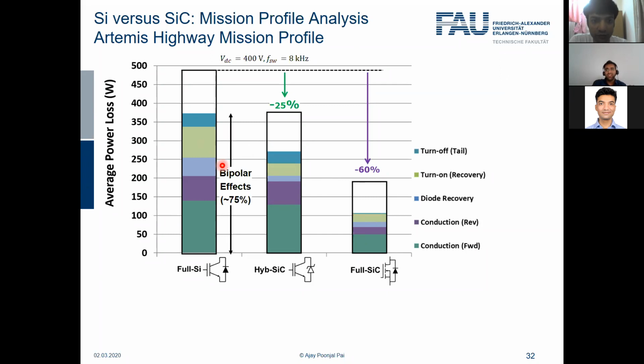Now what is missing is the tail. The IGBT has a tail current, which is missing in case of a SiC MOSFET. But in a hybrid device it still exists, because we are using the same IGBT and changing only the diode, and tail current is not affected by the diode. So we are already saving quite a lot of power losses by using a silicon carbide MOSFET. What's important to stress is that these savings come from going from a bipolar device, such as the IGBT, to a unipolar device like the silicon carbide MOSFET. We get this saving irrespective of how fast we are switching, or what the DVDT or DIDT is. This comes simply from going from an IGBT to a MOSFET.